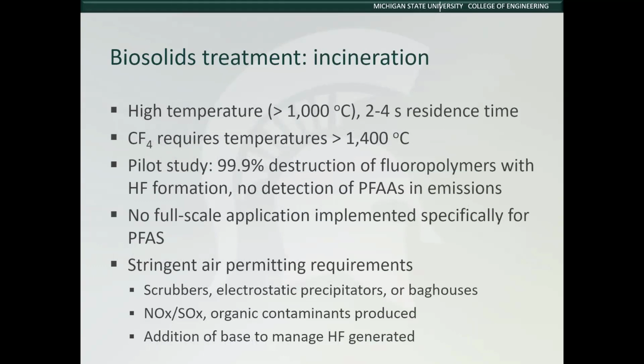The incineration of PFAS chemicals requires temperatures in excess of 1,000 degrees C and residence times in the range of 2 to 4 seconds. Compounds such as carbon tetrafluoride require even higher temperatures. In a recent EPA presentation, it was reported that 99.9% destruction of fluoropolymers was achieved with hydrogen fluoride formation.